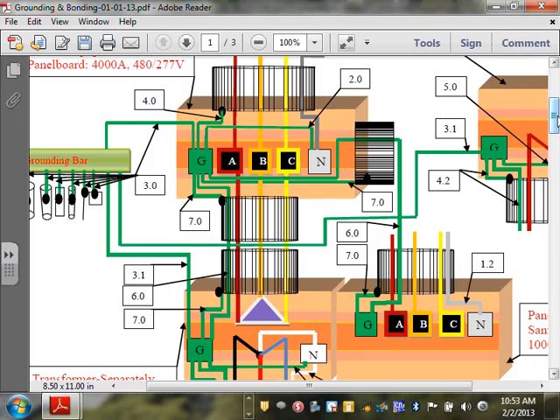What's the size of the equipment grounding conductor that we came up with? 2 AWG. It will be a 2 AWG. Exactly the same. It will be a 2 AWG. Now you have 2 options here. How many conduits did we say are going to be coming out of here to the 1000 amp? 4 conduits, based on my example. You're going to have 4 rigid coming from underground to the feeder. 2 options, the same thing.